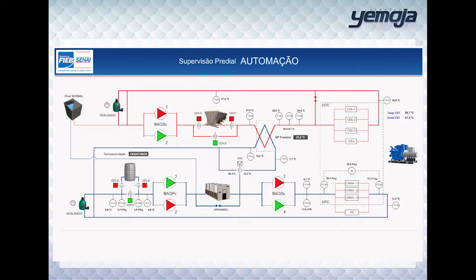Here in this other cycle, the red cycle, we have dry coolers, which are meant to cool down the water that flows within this red cycle whenever the external temperature is below about 26, 27 degrees. And these pumps here are all redundant.